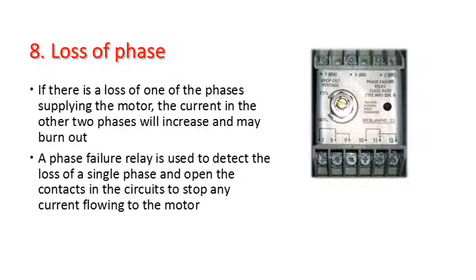If you have one phase lost in a three-phase motor, you have the other two phases trying to cope with the load, and the current increases, the motor runs badly, and it may burn out eventually. So we use phase failure relays to detect the loss of a single phase and open the contacts so that the current stops flowing to the motor.